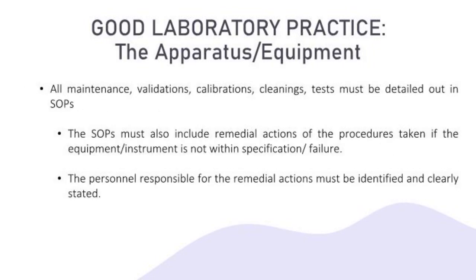Thus, all the protocols and procedures for the maintenance, validations, calibrations, cleanings and tests must be clearly laid out in the SOPs. The SOPs must also state the remedial actions should the equipment face any failure or malfunctioning. The SOP must also indicate the person in charge for taking these remedial actions and must be clearly stated.